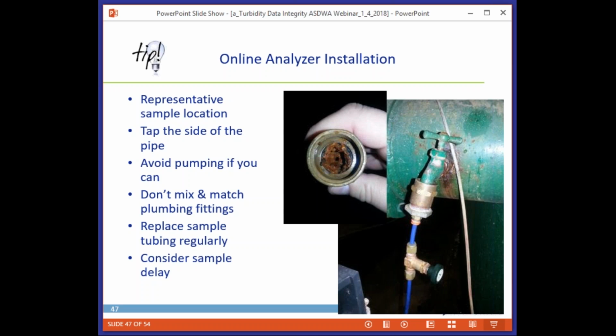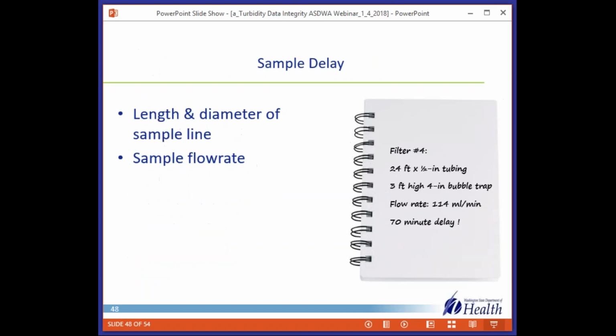I don't want to give the impression that we don't think being frugal is good, but it's where we're saving the money. So some of the tubing we've seen is amazing, maybe never replaced. It's relatively cheap, and that can have a big impact on the quality of the water that you're sending to your turbidimeter. And you should consider sample delay. So we're going to talk a little bit more about that.